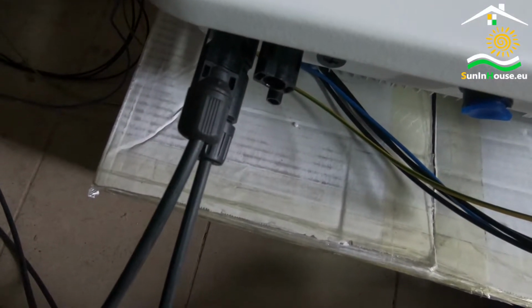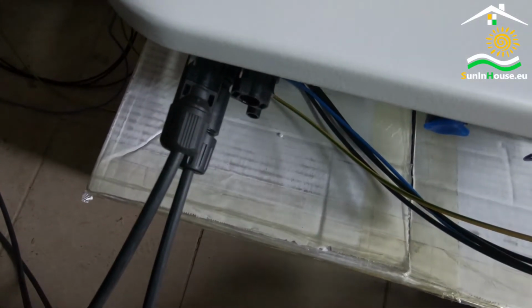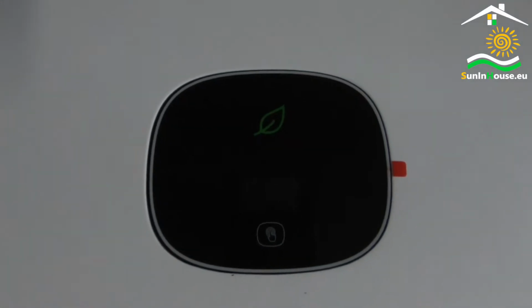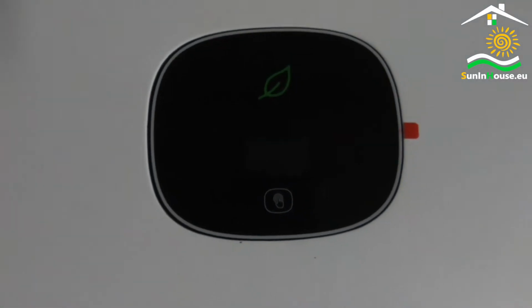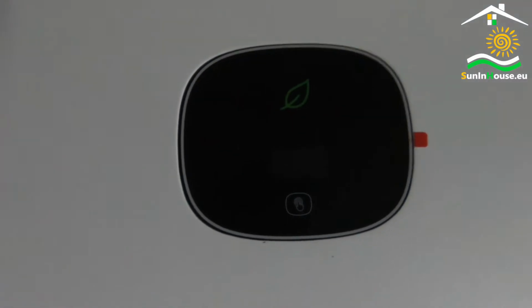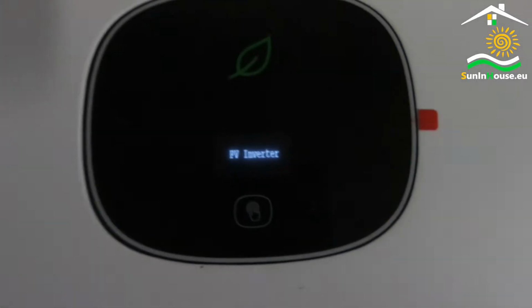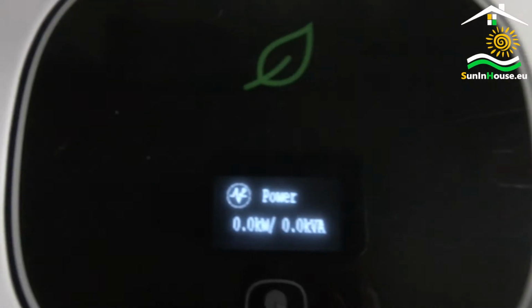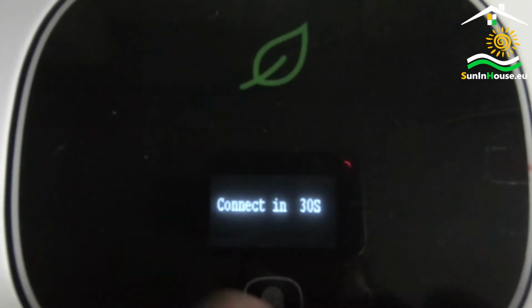We also check whether we have the expected voltages on the DC circuits. Here also provisionally connected on one DC circuit. If after checking we find that we have no problems, turn on the DC circuit with the switch. The inverter starts up. For starters, maybe a short training in command handling.